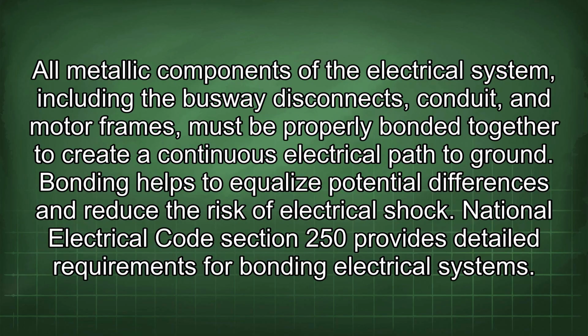Fifthly, bonding is important. All metallic components of the electrical system, including the busway disconnects, conduit, and motor frames, must be properly bonded together to create a continuous electrical path to ground. Bonding helps to equalize potential differences and reduce the risk of electrical shock. National Electrical Code Section 250 provides detailed requirements for bonding electrical systems.